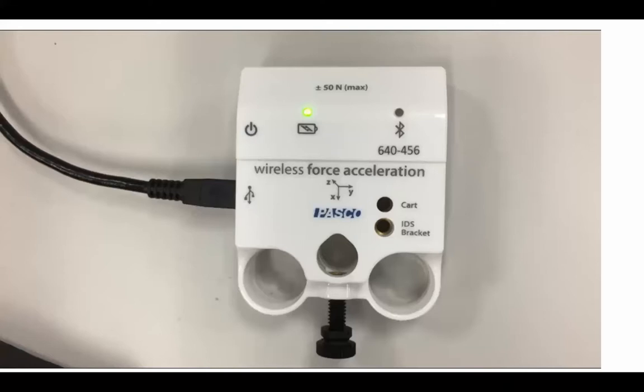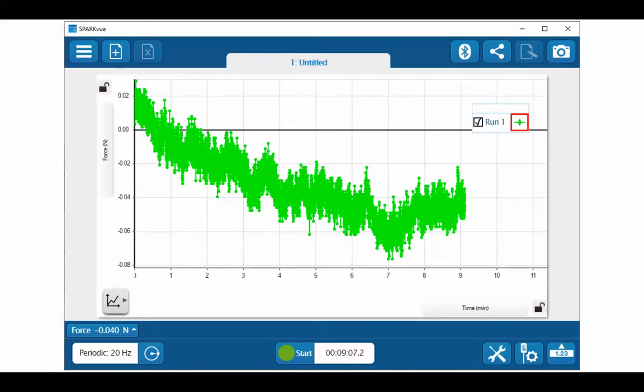The load cell within the wireless force acceleration sensor contains a strain gauge, which is a resistor. In order to get to full operating temperature, the wireless force sensor must remain on for a certain amount of time. You can see here the data that was taken from a sensor that had not yet been warmed up. You can see there is some small drift that after a certain amount of time completes moving. When that's happened, that means that your sensor is ready to be zeroed, and then after that, ready to be calibrated.